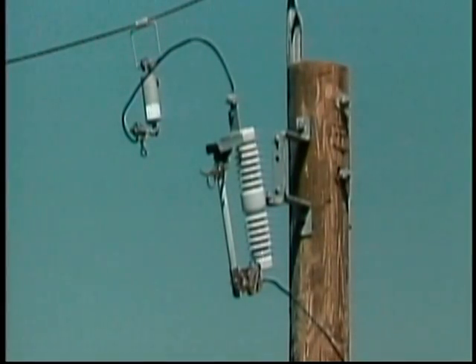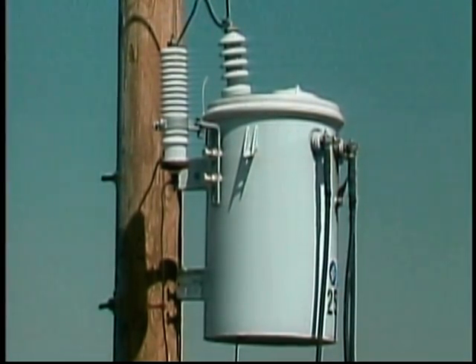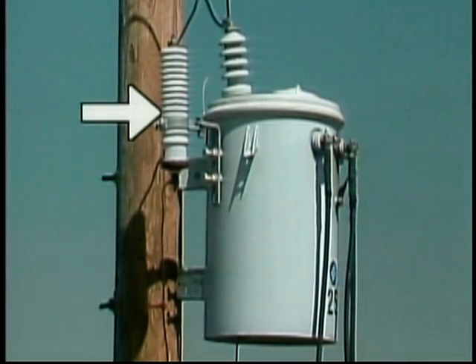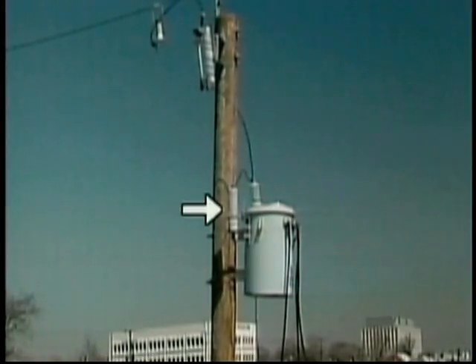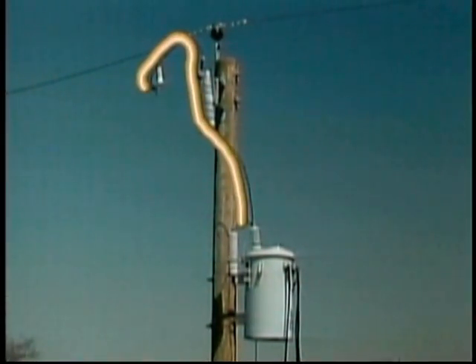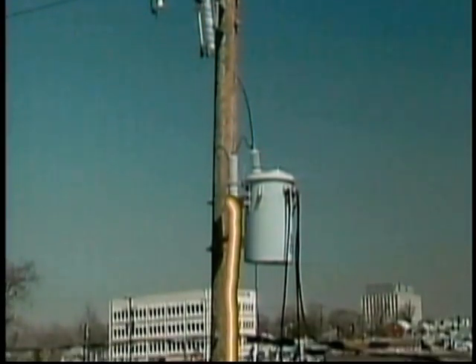A component sometimes used with fused cutouts is a current limiting device. A current limiting device protects system equipment by limiting current flow to the equipment during fault or short circuit conditions. Distribution equipment and lines may also be protected by surge arresters. A surge arrester protects against damage from excessive voltage surges, such as surges caused by lightning or switching. An arrester is typically mounted on or near the line or equipment it protects and is connected to the line at one end and to a ground at the other end.